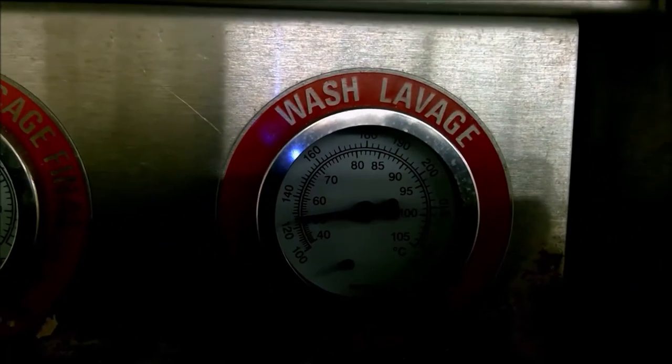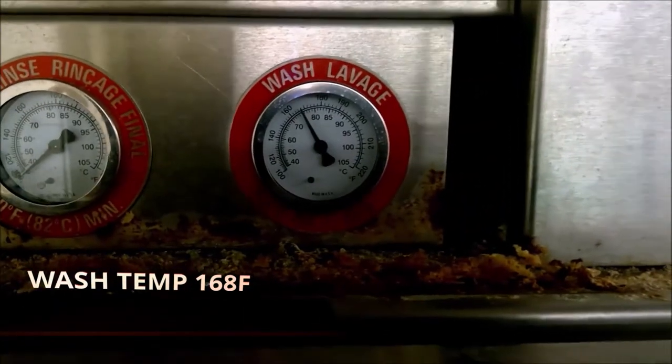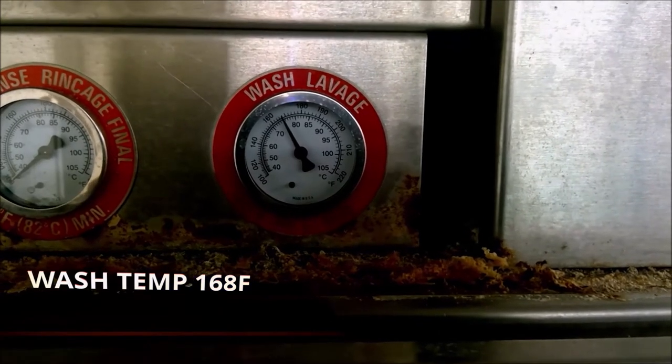Temperature is coming off of 120, so it is rising. We are heating. Alright so we've cycled off. Plunger is no longer pulled in. We cycled off at 168 Fahrenheit.